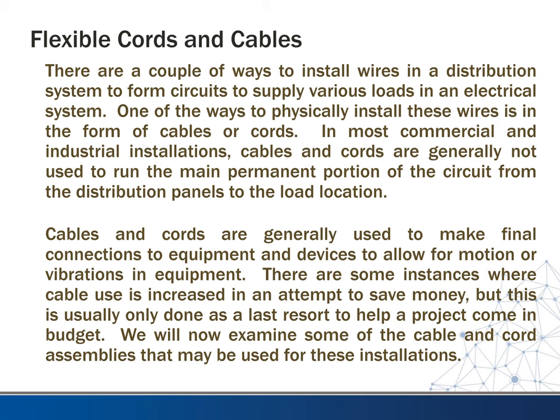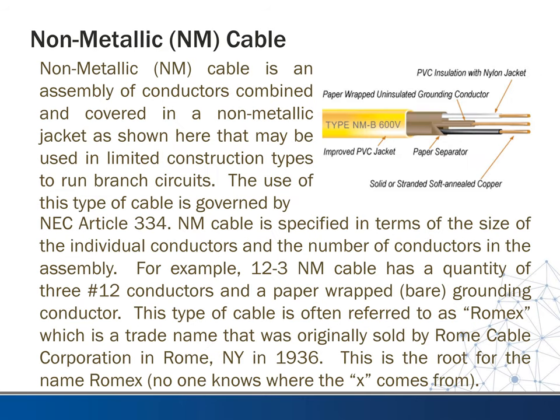Now we want to examine some of the cable and cord assemblies that may be used for these installations. One of the first is non-metallic cable, referred to as NM cable. This cable is an assembly of conductors combined and covered in a non-metallic jacket, as shown in the picture on the right, and may be used in limited construction types to run branch circuits. The use of this type of cable is governed by NEC Article 334.